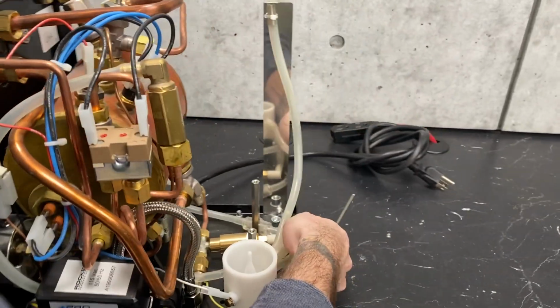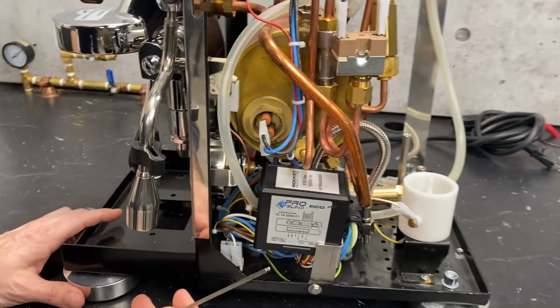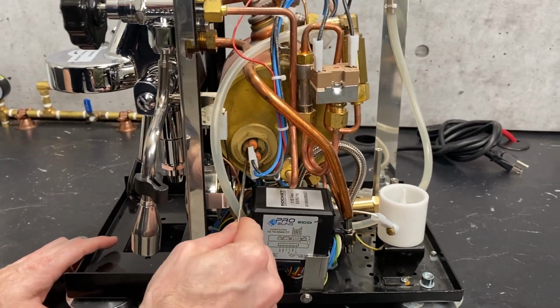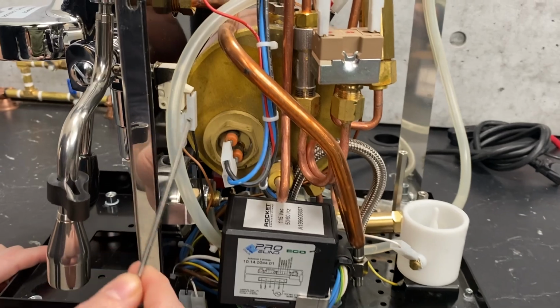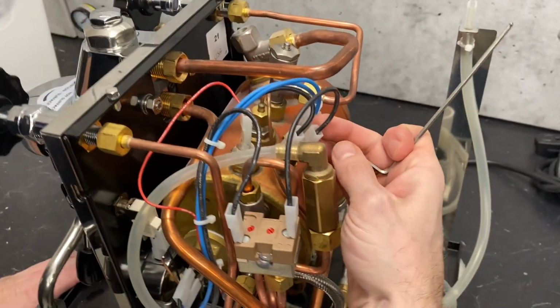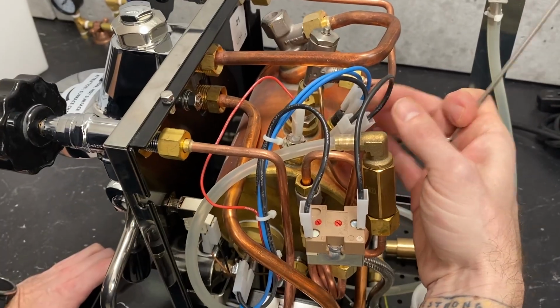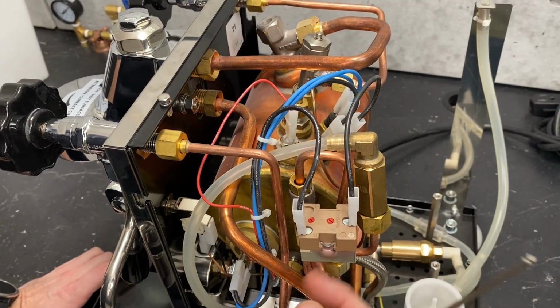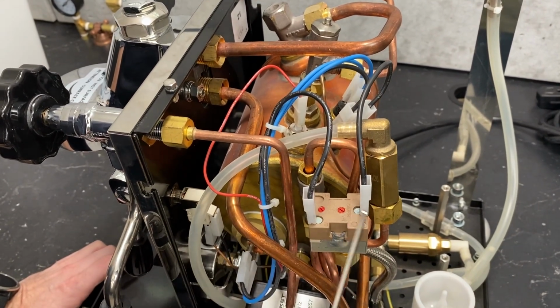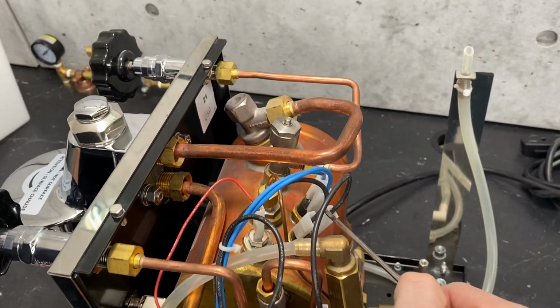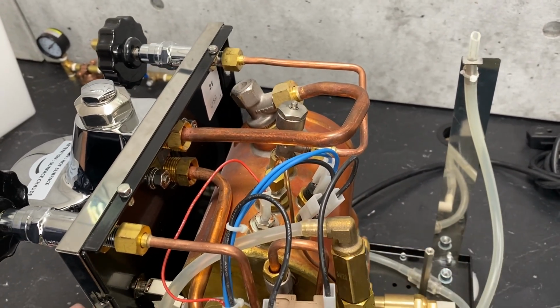Back over to this side, we've got your heating element. The heating element comes off of your thermostats here. This thermostat comes off of your Pressurestat. So power comes in, comes out of here when it's calling for it, goes through there, down to the element.